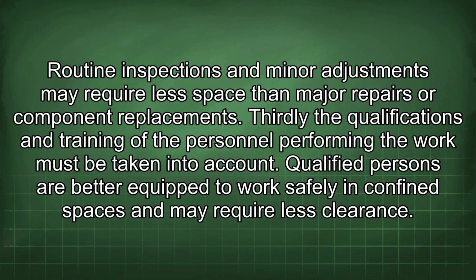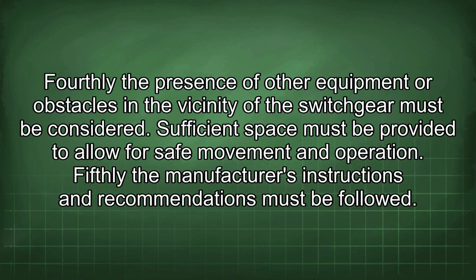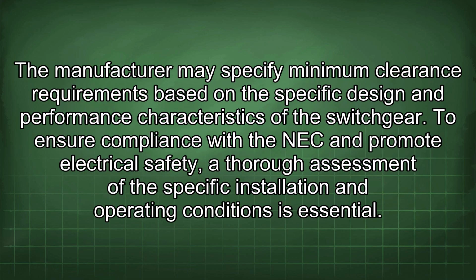Thirdly, the qualifications and training of the personnel performing the work must be taken into account. Qualified persons are better equipped to work safely in confined spaces and may require less clearance. Fourthly, the presence of other equipment or obstacles in the vicinity of the switchgear must be considered. Sufficient space must be provided to allow for safe movement and operation. Fifthly, the manufacturer's instructions and recommendations must be followed. The manufacturer may specify minimum clearance requirements based on the specific design and performance characteristics of the switchgear.